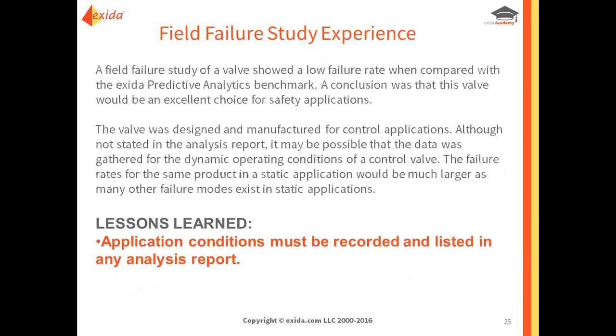And here's a third example. A field failure study of a valve showed a low failure rate when compared with the exida predictive analytics benchmark, and the conclusion was that this valve would be an excellent choice for safety applications. Well, the valve was designed and manufactured for control applications.